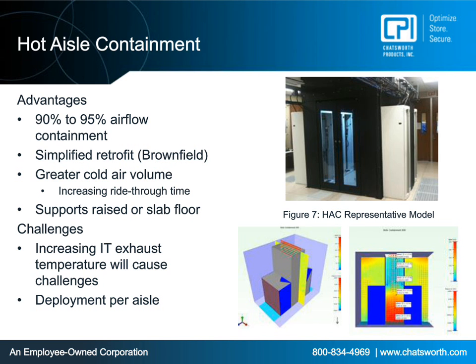And with hot aisle, you can do raised floor, you can do slab floor. Once you contain the entire aisle, we can get your airflow however which way you want. You don't need to be on a raised floor or on a slab. You can be on either. It doesn't matter. The challenge is when the temperature starts to rise. We see right now at the back of the cabinet 114 degrees. In some cases, it's usually above 100 at the top end. 114 is what we've seen. It is going to go in a few years hotter than that. It is going to be in the 120s in the back of the cabinet. So working on the back side of that cabinet is going to be challenging.